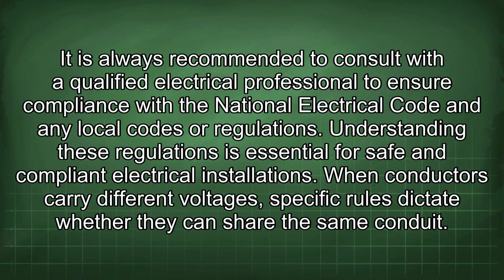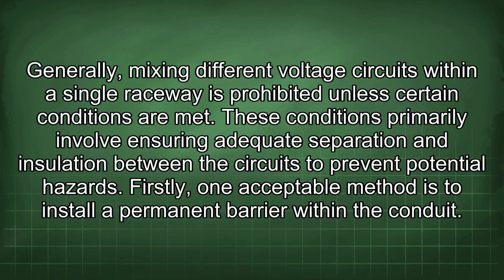When conductors carry different voltages, specific rules dictate whether they can share the same conduit. Generally, mixing different voltage circuits within a single raceway is prohibited unless certain conditions are met. These conditions primarily involve ensuring adequate separation and insulation between the circuits to prevent potential hazard. Firstly, one acceptable method is to install a permanent barrier within the conduit.